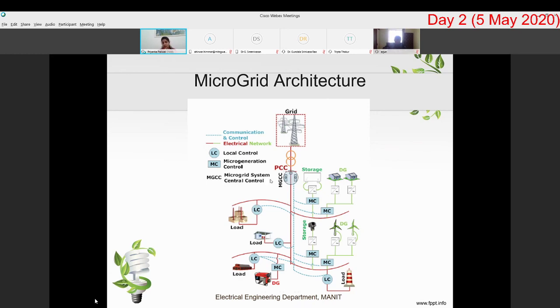This MGCC also controls the voltage and frequency at the point of common coupling. The microgrid central controller also decides whether the microgrid should operate in connection with the grid, that is in the grid-connected mode, or in the islanded mode. This decision is also taken by the microgrid central controller only.